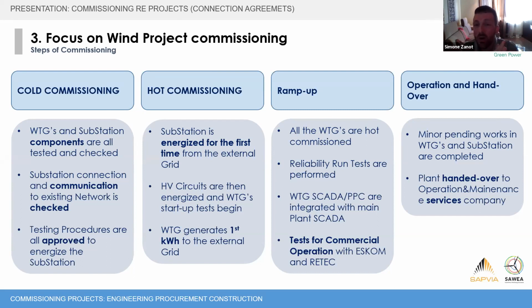The ramp-up period is when, from the first to the last WTG or power conversion unit, all are hot commissioned. Reliability tests are performed and passed, and very importantly, the SCADA and the PPC - basically a big laptop, for those not familiar with these acronyms - collect information signals from the network and from the wind turbine or power conversion unit. This big laptop receives all the information, and based on inputs from the grid, it responds and commands the turbine or power conversion unit how to behave.